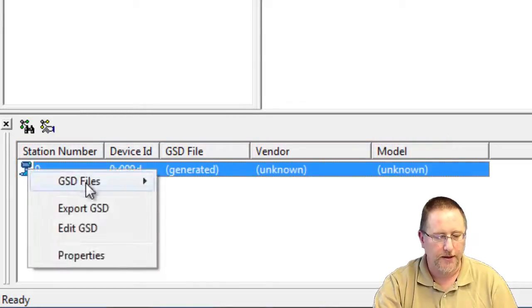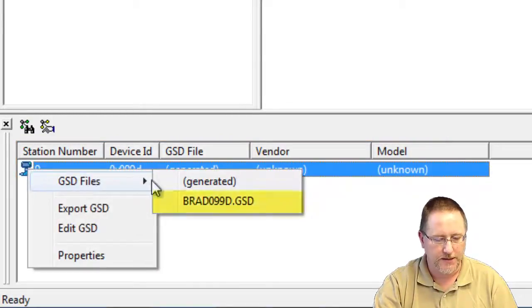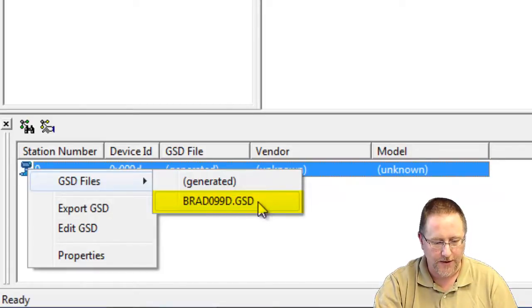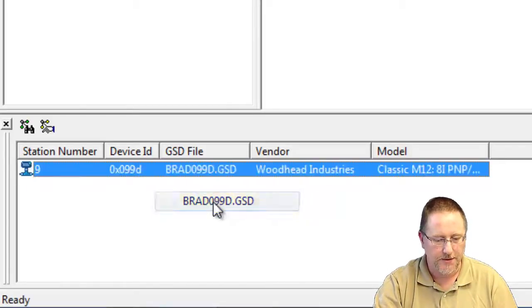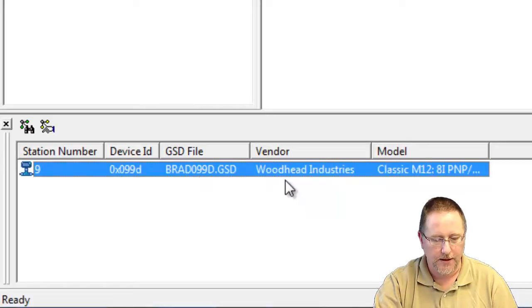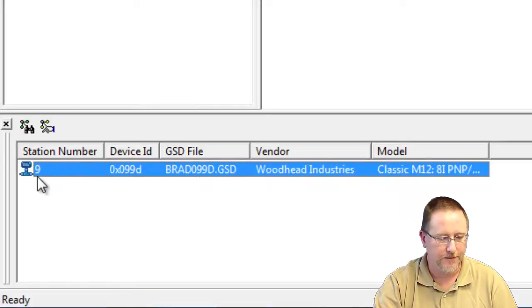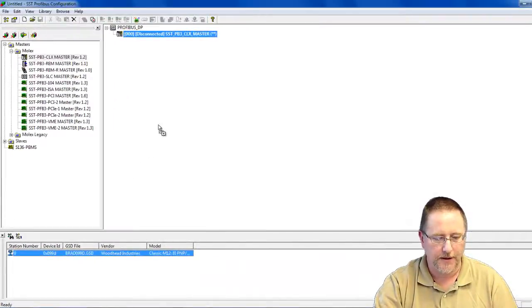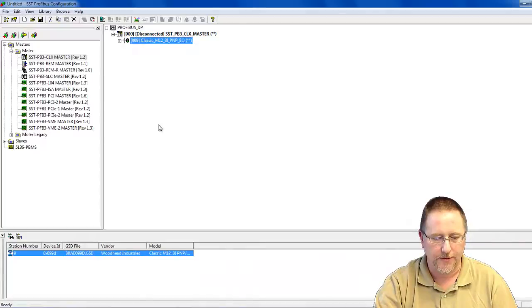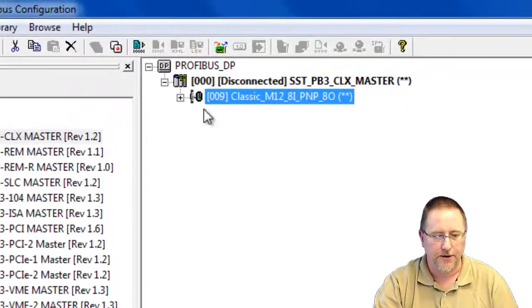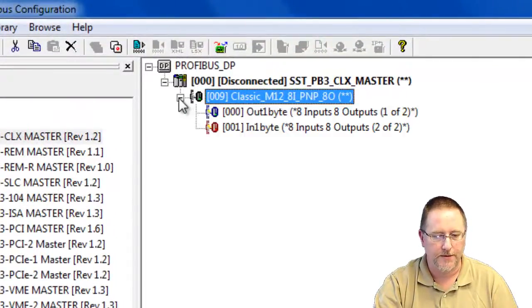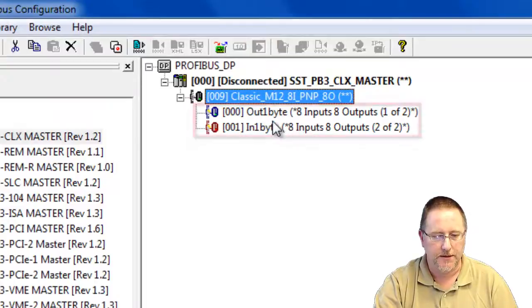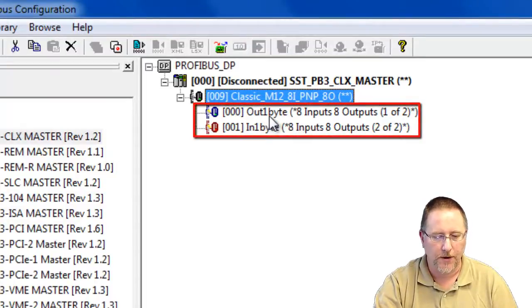So we're going to right click, select GSD files, and I already have the GSD file imported into the library for that device. So I'll select it. And now that fills in the file name, the vendor name, and the model. So I'm going to left click and drag that up to my window. It shows up underneath the master. We expand that. We just see it's one byte of output data and one byte of input data.